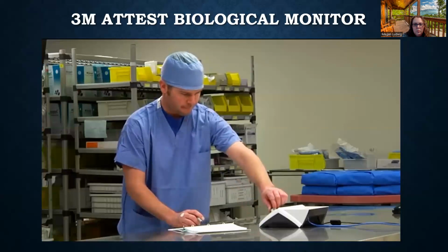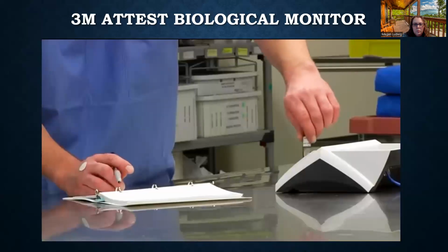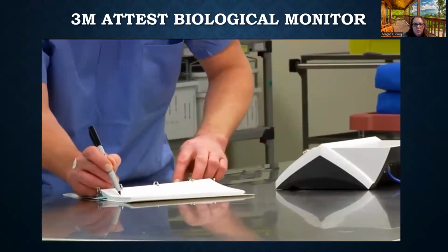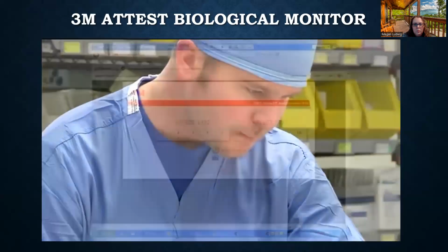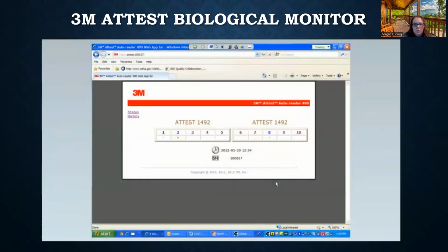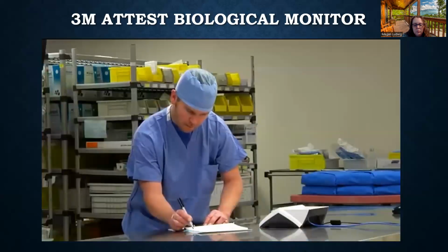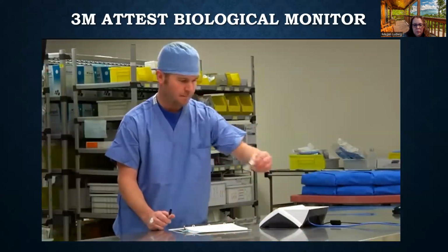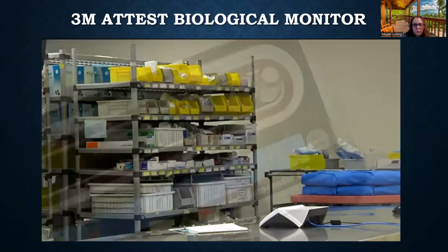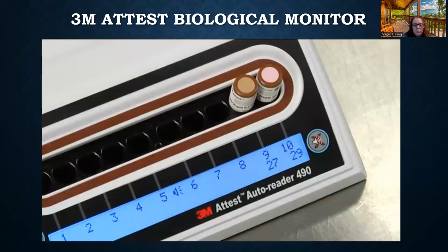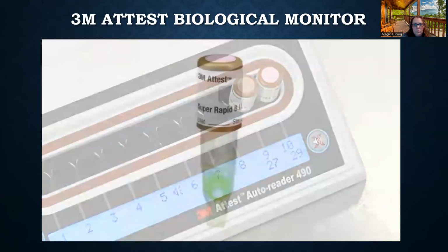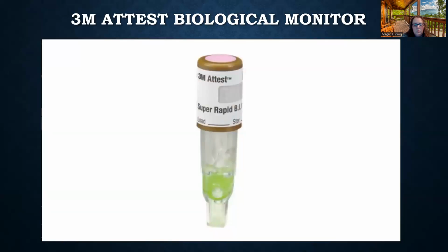After a BI test is complete, the next step is to record your results. You can use traditional record-keeping methods or the 3M Attest Auto-reader 490 web app. The 1492 VBI is normally discarded after the fluorescent result has been recorded. But if you're conducting a special study, you have the option to further incubate 1492 VBIs for a visual pH color change result. In the case of the positive control BI, you will see a yellow color change of the growth media and/or nonwoven material within 48 hours.